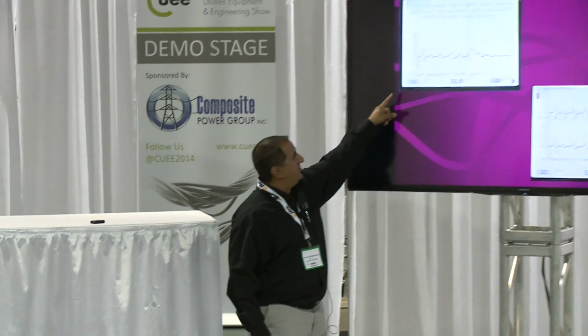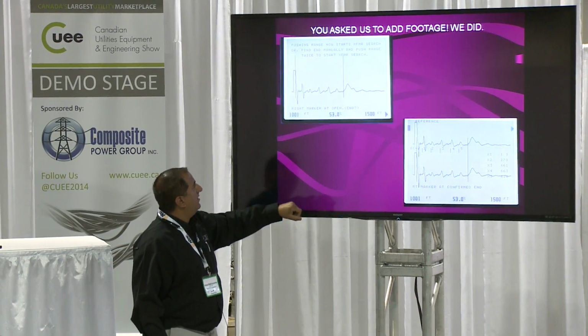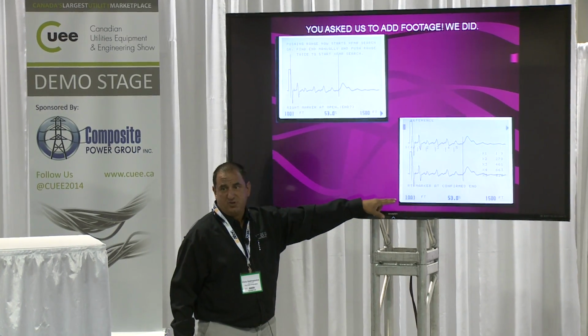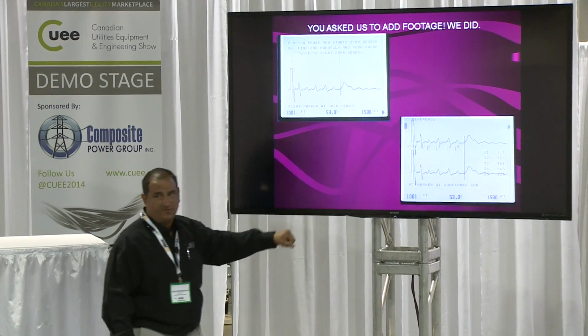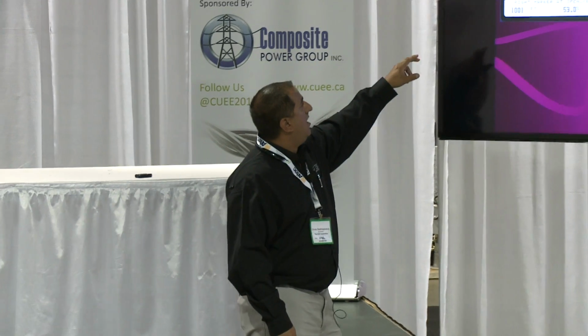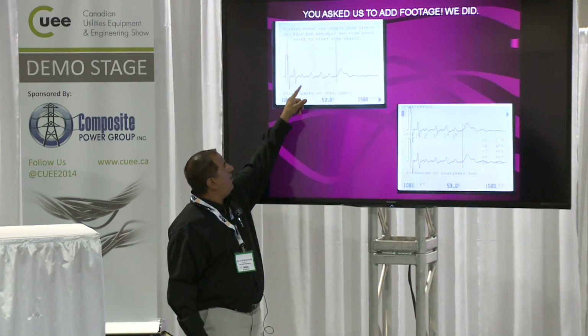One of the other features that the small unit has built in is for sectionalizing. So up here, we see the end of our cable is 1,000 feet. Down here we see it's the same cable we're testing. That's also at 1,000 feet. All this in here, we call those impedance changes, right? That's what we had on the other cable we tested. It was just a straight line. This one here, those are all transformers. So now we can use a small unit like that.